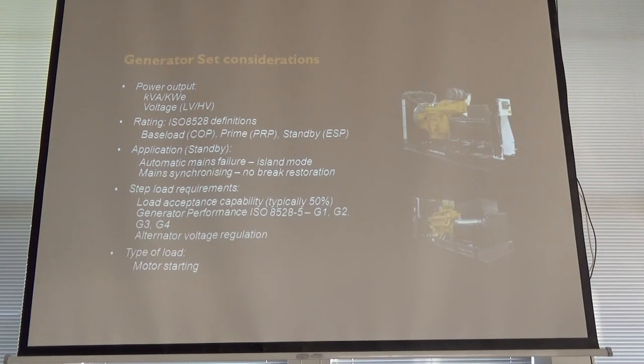There is a key thing. One is the application, and then the other is the rating of the genset for that application. So your application may well be standby for a hospital or for, say, a new building. A new building might be a life safety unit where if it's needed, it's a highly unlikely event, but if it's needed, it might only need to run for 3 or 4 hours for people to evacuate the building, that's it. The fire officer's happy with that sort of period of running. So it's a standby application, but you can have a standby rated set for that standby application.